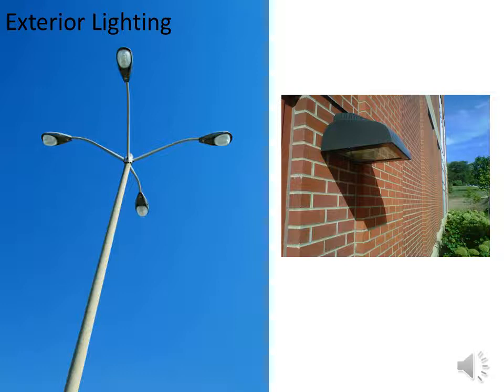Inefficient outdoor lights can range from metal halide with magnetic ballast to low-pressure sodium lamps. Low-pressure sodium lamps produce the yellowed color light that is typical of old streetlights. These lights have a poor color rendering index that makes it difficult to render the color of a given object under the light. New outdoor lighting has a much better color rendering index so that colors can be seen better at night. In addition, the total lumens, or light intensity, per watt is much higher, which is referred to as lighting efficacy. One important note is that Ameren Illinois owns some of the exterior pole lighting where customers rent the fixtures from Ameren Illinois. This lighting is not eligible for ActOnEnergy incentive money. The incentives available for exterior lighting are 30 cents per watt reduced.